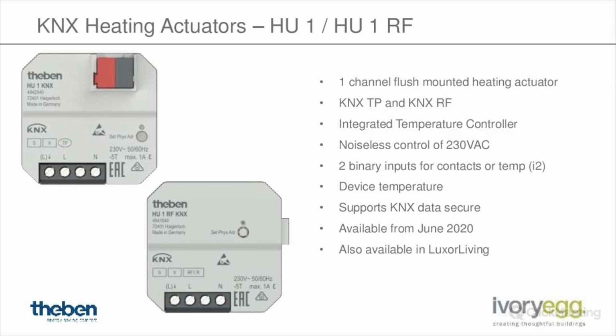And you've got an output, and it's a triac output, so it's silent switching of 230 volt, designed for valve heads, not designed for pumps or anything. It is just designed for valve heads. It's got internally, it reads its device temperature. So if you're mounting it in a back box or mounting it in an enclosed space, you can monitor the device and make sure that it's not overheating, which is separate to the binary inputs, which have two binary inputs, one can be used for temperature, which is on input 2. So supports data secure as well, as everything is now, pretty much all new products.